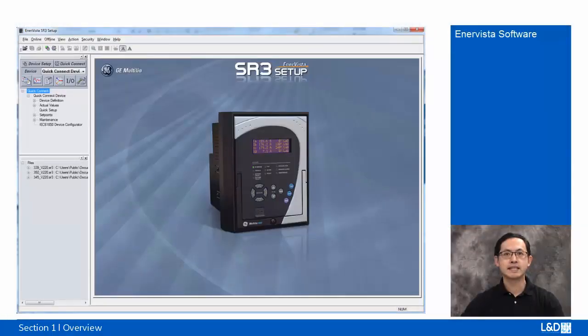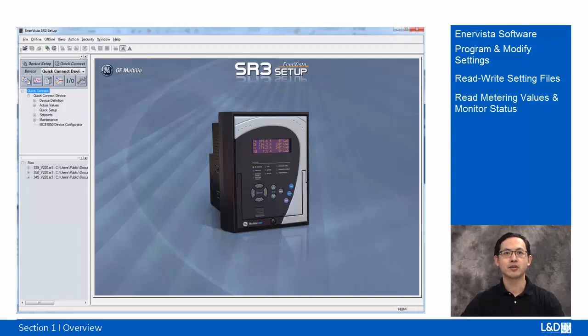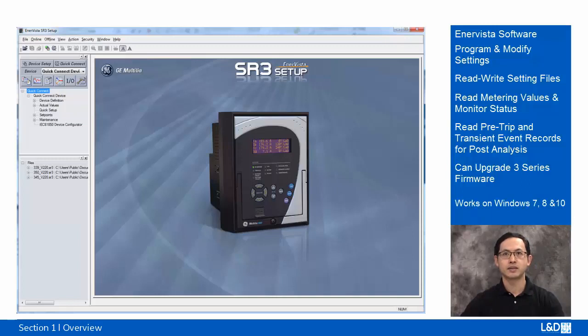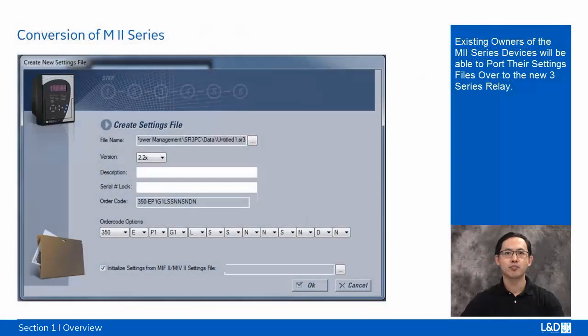EnerVista SR3 Setup software is one software that works for the 3 types of relays. It can program and modify settings, read and write setting files, read metering values and monitor status, read pre-trip, transient, and event records for post-mortem analysis, and upgrade 3 Series relay firmware, and each relay has its own firmware. EnerVista SR3 setup works under Windows 7, Windows 8 and Windows 10. M2 family relays MIF, MIV setting files can be imported into the 3 Series platform.